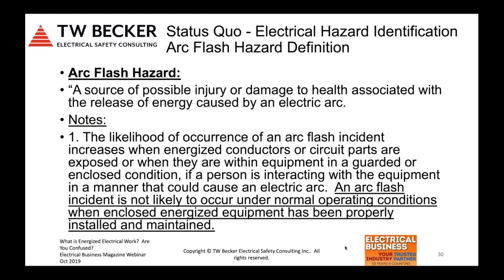The arc flash hazard, again, should be well identified. Again, lots of training happening. The definition is a source of possible injury or damage to health associated with a release of energy caused by an electric arc. And what I've underlined, this definition is from 70E and Z462, is the note that an arc flash incident is not likely to occur under normal operating conditions when enclosed energized equipment has been properly installed and maintained. That's really important, but it is a subjective determination of arcing fault probability and what is normal operating conditions.